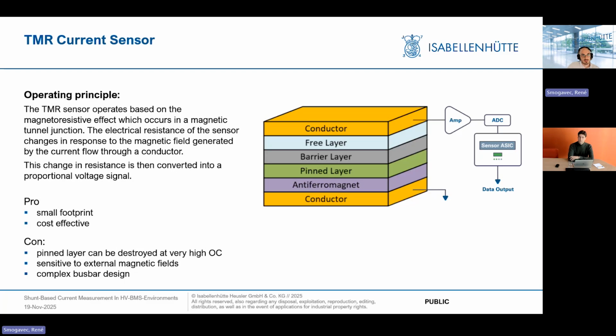There are also different styles like the TMR, a small device typically placed close to the conductor that reacts to the magnetic field and in turn changes its electrical resistance, which is a magnetoresistive effect. The resistance change is then converted into a proportional voltage signal. It's small and cheap, but orientation can unfortunately lead to high tolerance variation and thus can easily be very inaccurate, which is why it's mostly used as a hybrid solution in combination with, for example, a shunt.